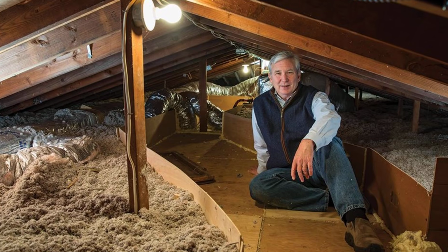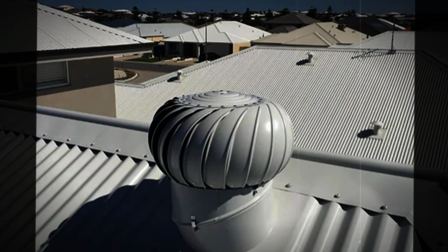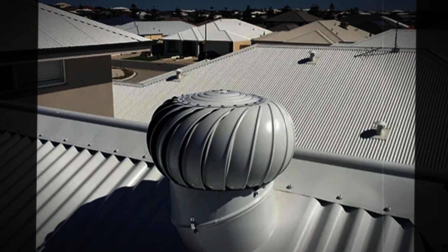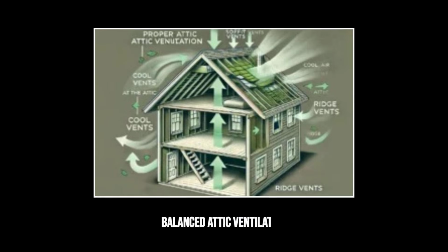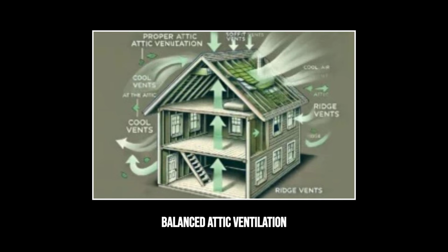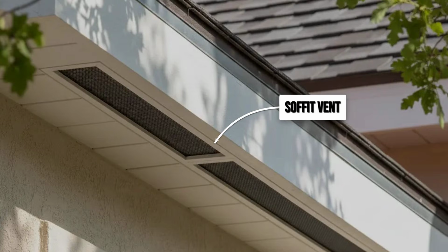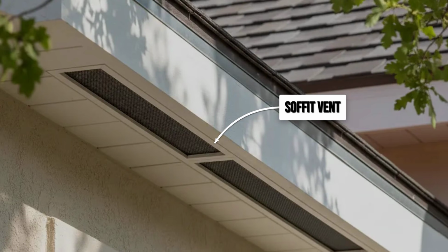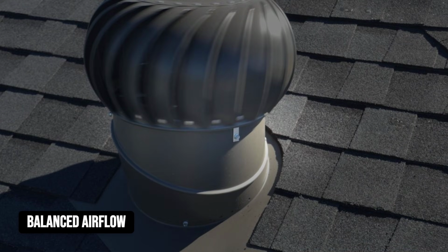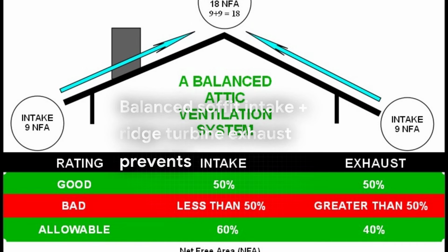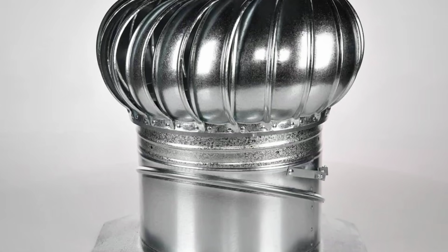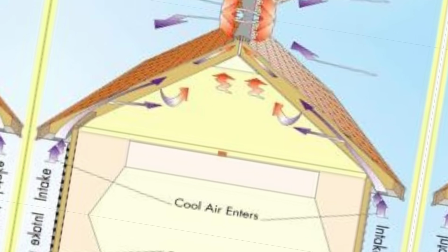The modern solution is not a hardware fix, but a systems understanding that was largely absent from installation guidance in earlier decades. Properly designed attic ventilation treats intake and exhaust as a balanced system. Soffit vents at the eaves provide the intake path. The turbine at the ridge provides the exhaust. When the system is designed correctly from the start, with matched intake and exhaust areas and no competing exhaust points, short-circuiting does not occur. The problem was never the turbine. It was installing the turbine without understanding the system it needed to work within.